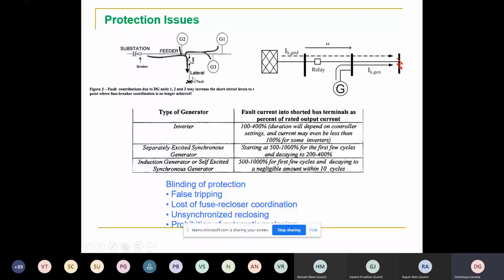What is happening is called blinding. Each inverter can inject only a certain amount of fault current, whereas synchronous and induction generators inject much higher fault current during a fault situation. So your DG is unnecessarily blinding the protection system. Also, sometimes one DG connected on another feeder may feed the fault in another feeder, and if the fault current is higher, the healthy feeder also gets separated out.